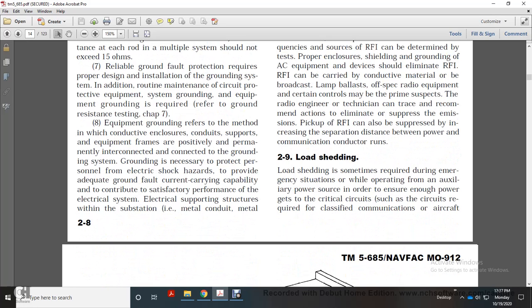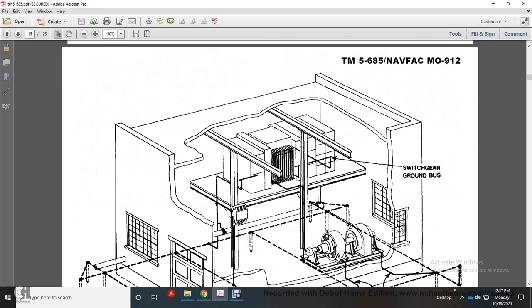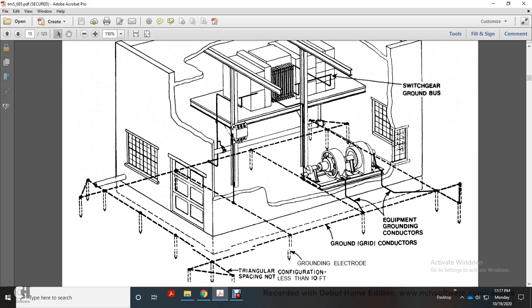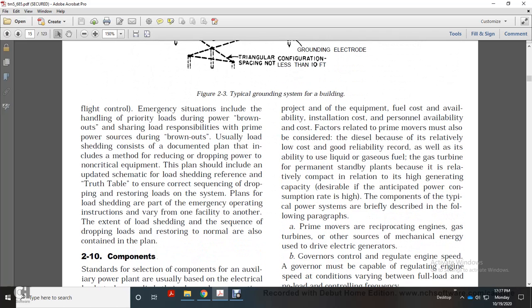Load shedding is sometimes required during emergency situations while operating on auxiliary power, in order to ensure that enough power reaches critical circuits. Load shedding during brownouts includes handling priority loading. It usually consists of a documented plan that includes the method of reducing or dropping power to non-critical equipment. The plan shall include an updated schematic for load shedding, referencing a truth table to ensure the correct sequence of dropping and restoring loads within the system.